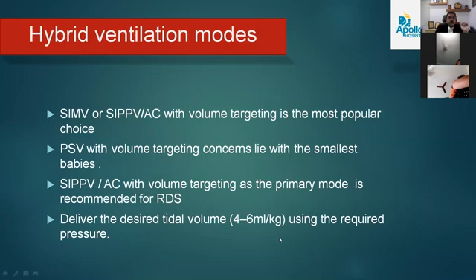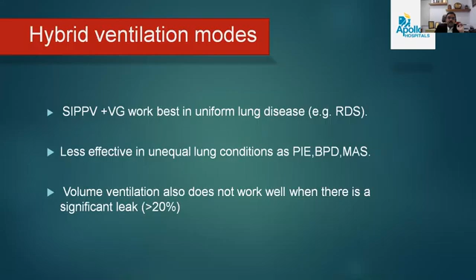SIPPV with volume guarantee works best in uniform lung disease. It is less effective in unequal lung conditions such as PIE, bronchopulmonary dysplasia, and MAS. Another very, very important thing is the ET tube leak. Please watch the ventilator when you're ventilating, and all these ventilators will show you the leak. If the leak is above 20%, your volume ventilation will not be appropriate, or you will not be able to give adequate volume to your baby. Ventilators like SLE and Dräger claim to have an inbuilt mechanism to overcome up to 50% leak in the ET tube. But even then, it is generally recommended that if you are seeing more than 20% leak in these babies, it is better to extubate and re-intubate them.